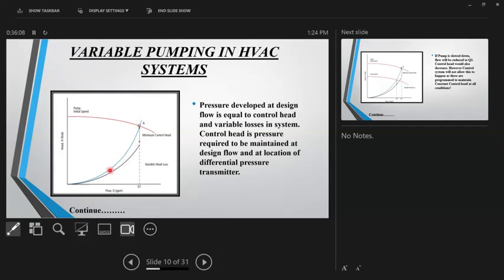So this blue curve can be resolved into two components. One is that fixed delta P setting, and the other is variable loss. This is a very important concept in the next slides. Control head is the pressure required to be maintained at design flow at the location of the differential pressure transmitter. So that value, 1 bar, 2 bar, or whatever, is this vertical axis distance, and this is the variable loss, which is a function of your flow. The fixed part is not a function of your flow; it's constant. Correct?